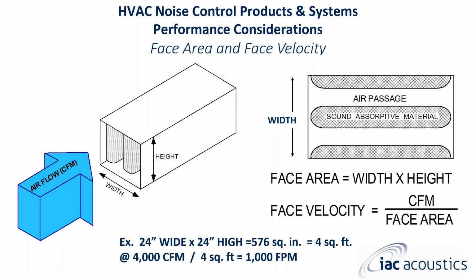When you're looking at the face area, that is width times height. So an example is 24 inches wide by 24 inches high equals 576 square inches. Convert that to square feet. That is then 4 square feet. Now, face velocity is CFM divided by your face area. So 4,000 CFM divided by your 4 square feet, you have 1,000 feet per minute.